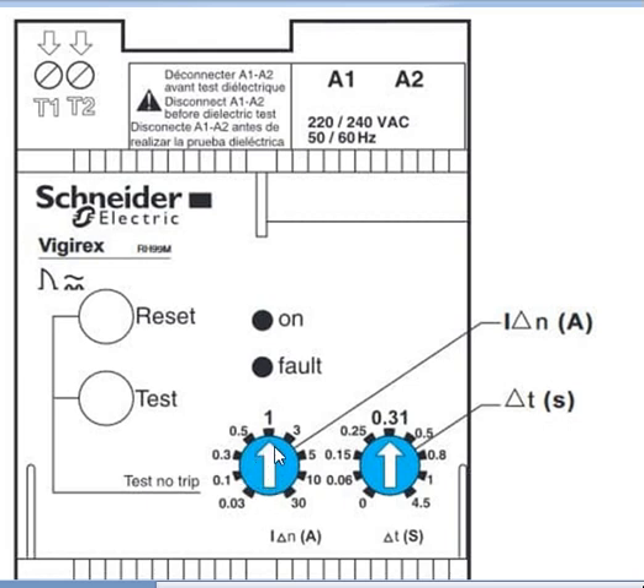So the first dial is going to select the leakage current, how much leakage current you would like to flow in the earth wire. So friends, the range is from 0.03 to 30. Normally for machines, generators and big loads, we need to select 0.1, and for normal lighting circuits and electronic equipment, we need to select 0.03. There are also other dials that are used in power stations.